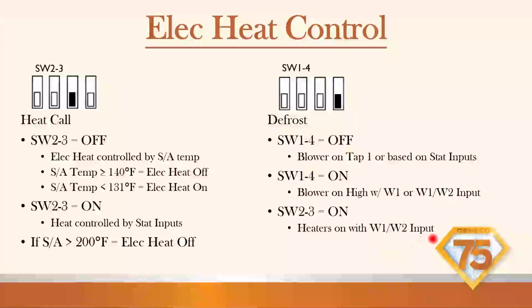Heaters on with W1, W2 input. Blower on tap 1 or based on stat inputs. So we allow the stat to control the W1, W2. So if we have 2 stages of heat, we're going to allow the thermostat to take control of when that second stage heat strip fires up.